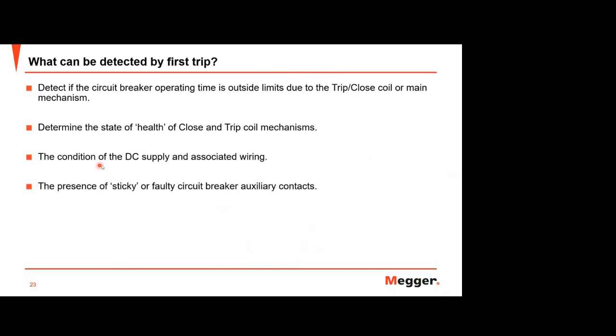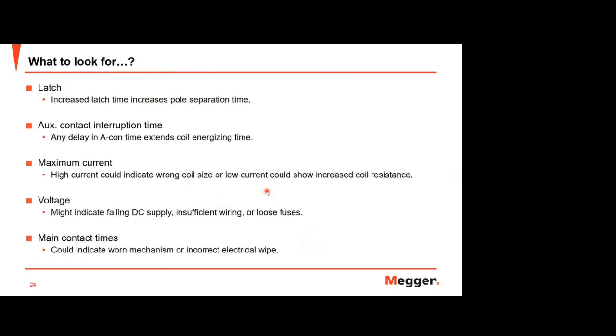And the condition of DC, of course, because DC has correlation with the coil current performance. The condition of the DC supply and wiring associated to the DC supply can also be detected. And the presence of sticky or faulty circuit breaker auxiliary contact. Even if very rare, there is still a possibility of failure on the auxiliary contact, and you can still detect it through this first trip.